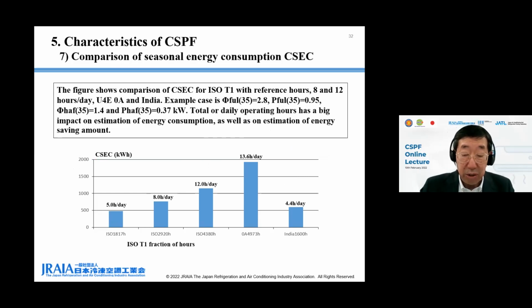The figure in this page shows comparison of cooling seasonal energy consumption CSEC for ISO T1 fractions with total 1,817, 2,920, and 4,380 hours, U4E 0A hours with total 4,973 hours, and Indian hours with total 1,600 hours. Each total hours correspond to 5.0, 8.0, 12.0, 13.6, and 4.4 hours per day.